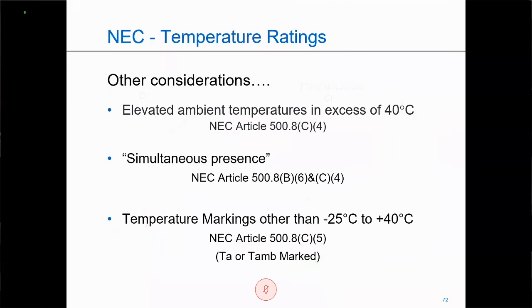Other considerations, and we started to talk a little bit about this earlier when we were talking about our standard temperature ratings. Anytime I'm in excess of 40 degrees C, it needs to be marked. When I have lighting fixtures, those lighting fixtures, as luminaires in a hot area, are not going to dissipate the heat as well, so it's going to affect my temperature.